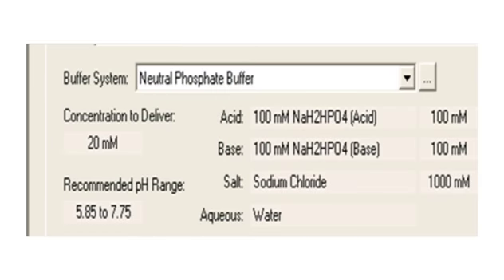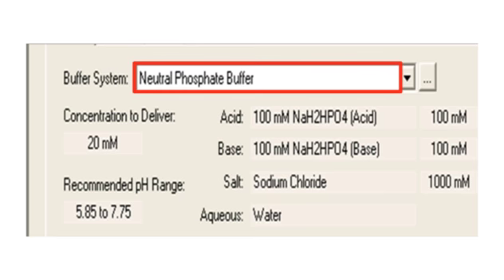Separate and independent curves can be specified for pH and ionic strength. Both pH and ionic strength can change simultaneously. The free adjustment of these two parameters can be useful in optimizing the separation for a particular protein mixture. It is not obvious, however, from this table how the solvent management system derives the desired buffer and salt profile from the four solvent bottles available to it, where it must reliably deliver the correct proportions from each of the four lines. The software calculates the percentage flow from each reservoir based on the information associated with the buffer system available as a drop-down menu. When the buffer is selected, the screen displays the information about what is in each of the four reservoirs, as well as the intended total buffer concentration and the usable pH range.